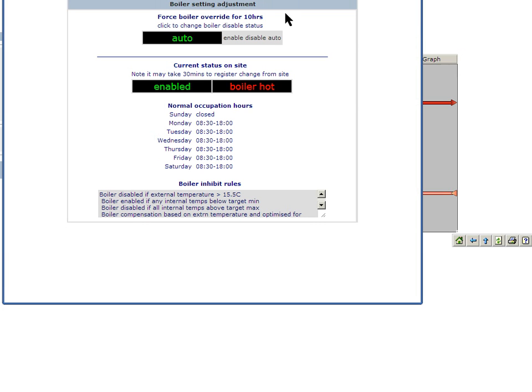At the top, there is a panel for setting the plant time override. This will be an exceptional adjustment, which will revert back to the default setting when the time set for override has expired. This can be set for single or multi-site operation to cope with public holidays, for example, where a site may be turned off or down for just one period.